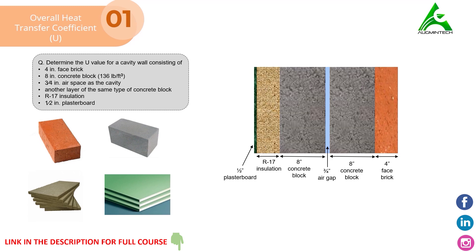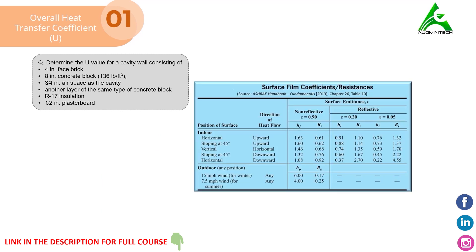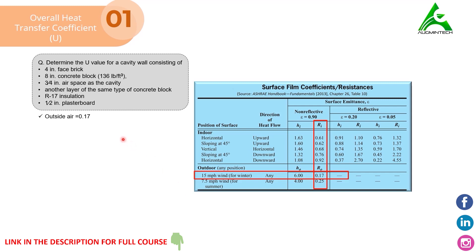Note that the right side of the wall is taken as outside the building and the left side is assumed to be inside. First, we'll find the R-Value of the outside air using the ASHRAE chart. In this chart, there are indoor and outdoor conditions. Because we are talking about the resistance of outside air, we select that row. We are considering winter conditions, and selecting the resistance column, these two intersect at the value of 0.17. So the resistance found for the outside air is 0.17.